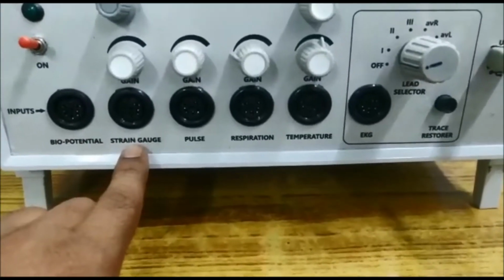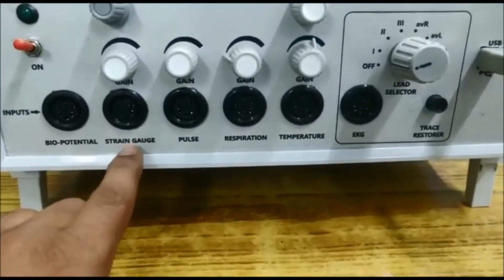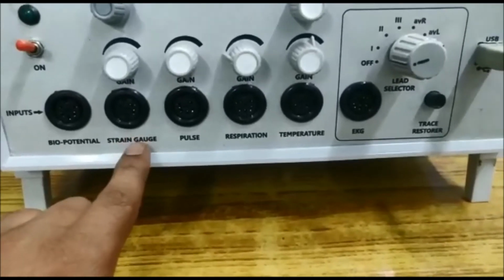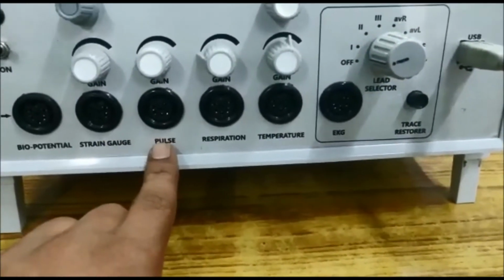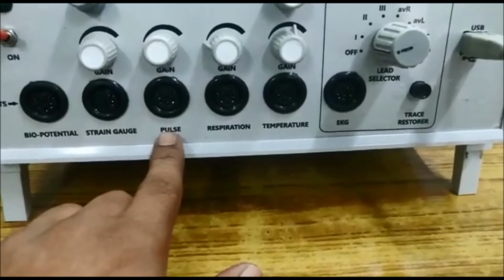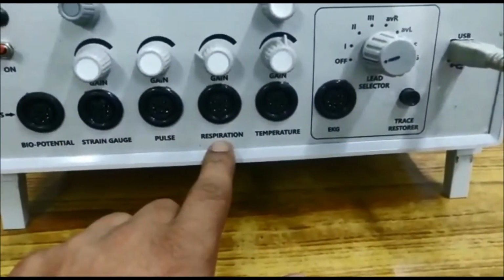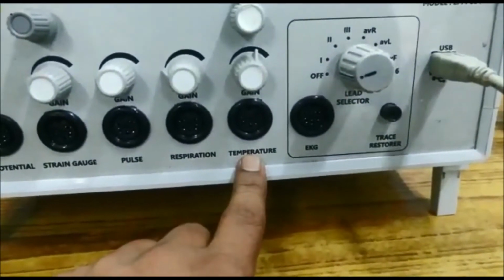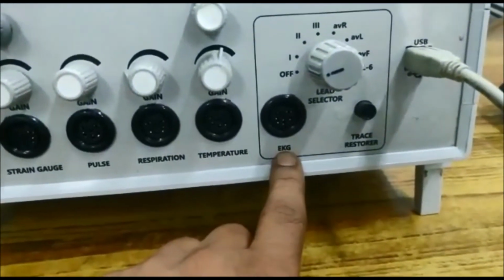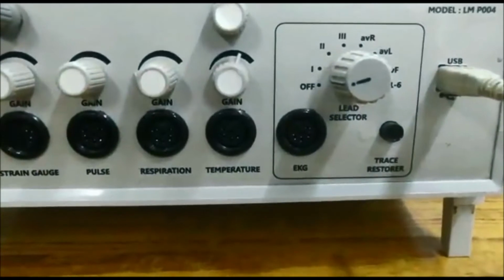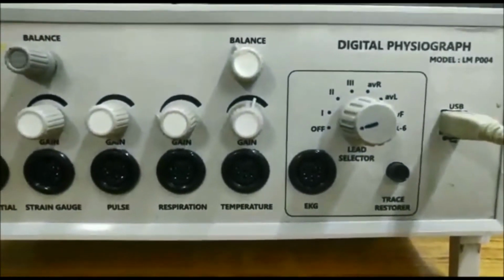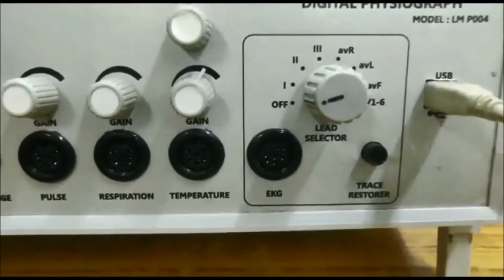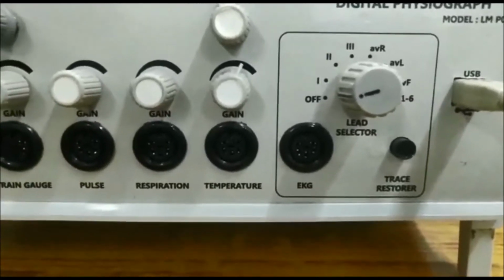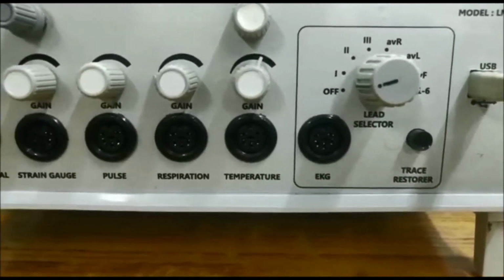This is the strain gauge. This is used for force, pressure, volume. This is the pulse input for finger pulse. This is the respiration input. This is the temperature input, and this is the EKG input. Now you can see here, this is the lead selector. You can attach all the 10 leads to the patient body, but you can only see one lead at a time on the software.